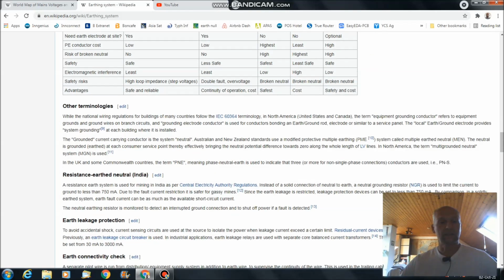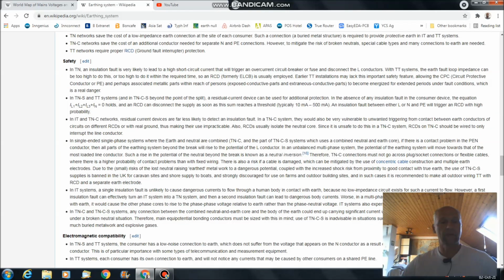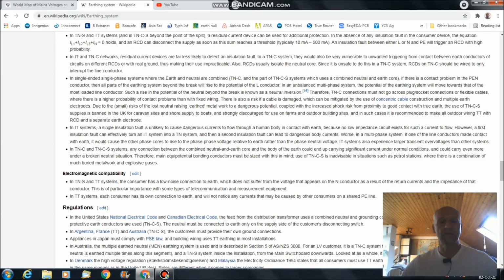We can take a closer look into that here. So here we have the explanation why the IT system is safe. In IT systems, a single insulation fault is unlikely to cause dangerous currents to flow through a human body in contact with earth, because no low impedance circuit exists for such a current to flow. So that is why the IT system, if you only use one appliance on it, is very, very safe.